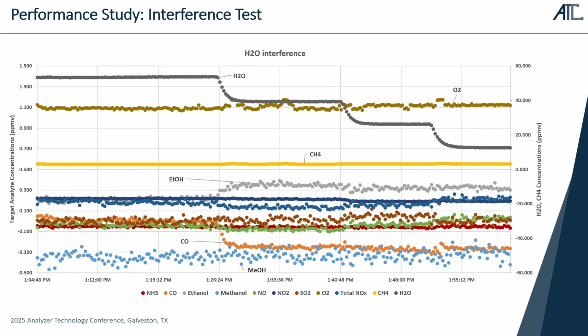And the last performance study was the interference test that was done by a third-party laboratory. So this was basically a ramping of moisture from 50 ppm down to 10 ppm to see the effect, if any, on additional components. And overall, all the impurities that were measured were unaffected by moisture, which is good because moisture is usually, from an FTIR standpoint, a primary interferent, along with carbon dioxide. But there were minimal effects from moisture, which allowed us to have a lot of confidence in our results.